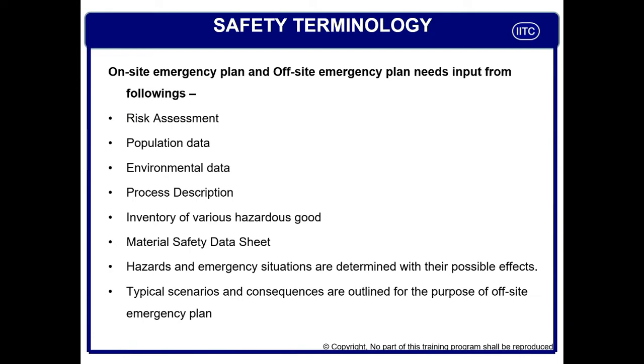These are key elements required when preparing your on-site emergency plan or off-site emergency plan. These inputs come from the risk assessment of your plant. You need population data of your plant as well as outside the plant, because in an emergency you need to remove people from your plant as well as from neighboring companies or societies. You must also know environmental data such as worst-case wind direction, highest wind speed, ambient temperature, and rainfall data.